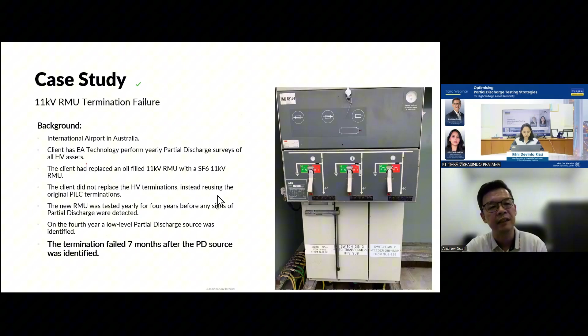So some of y'all may ask, hey Mr. Andrew, if you detected it, how come it still failed? Well, a lot of the time when a PD is detected, we inform our customer, but unfortunately they couldn't do the shutdown because certain RMUs or certain electrical assets are so limited, so they can't afford the shutdown. Because shutdown means maybe half a day, a portion of the airport has no power. Maybe your luggage belt cannot be used or some of the runway cannot be used. So they cannot afford that. So they request to wait. But unfortunately, after 7 months, this failure happens.